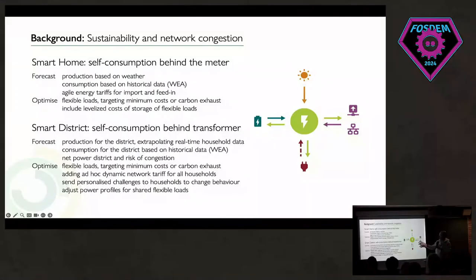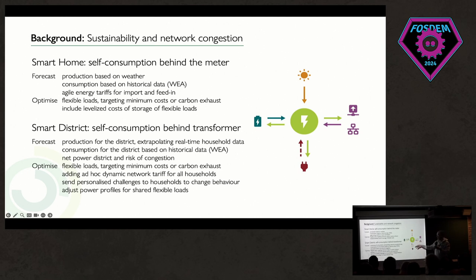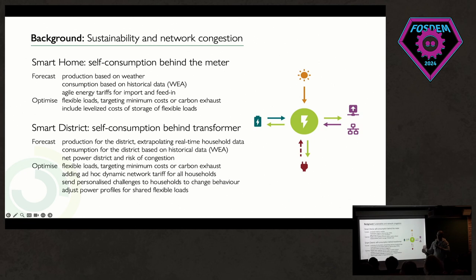What we are trying to optimize is minimizing the cost or carbon exhaust based on all this data. The system will control what we call flexible loads. Depending on the data, it can decide when to charge or discharge the battery, when to charge or discharge electric vehicles, or it can control heavy loads like heat pumps — where you have some freedom on when to power them up or adjust the temperature set point. This can be automatic, but it could also simply be manual by pushing information to end-users through the UI.